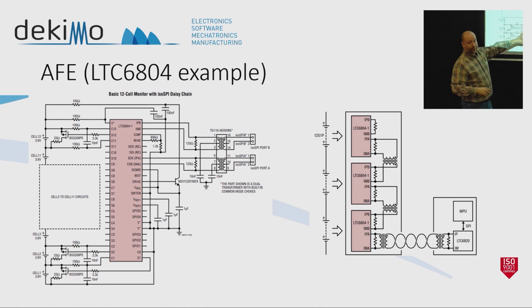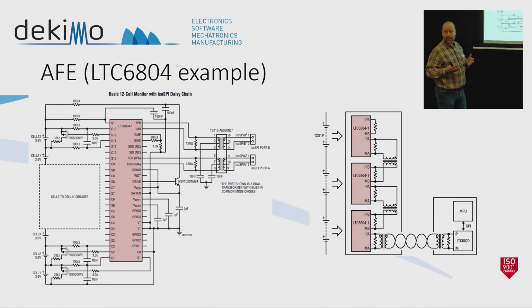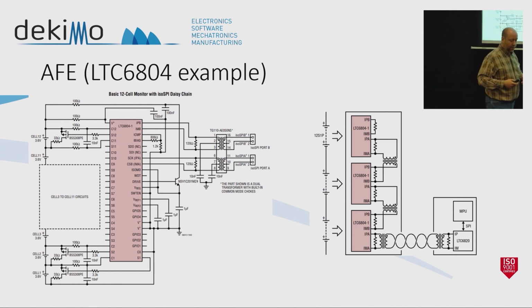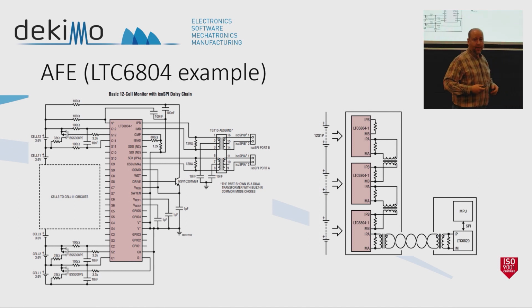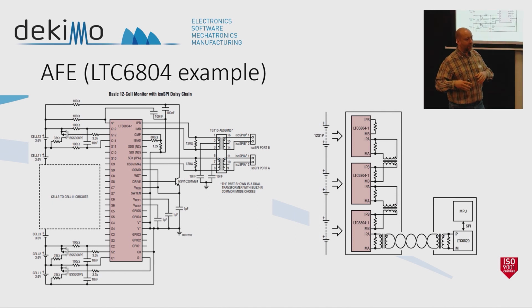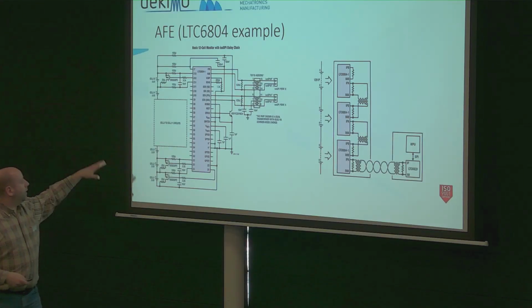The AFE can discharge every single cell separately in the battery pack. Then you have the chip, and a communication interface. What's often used in battery packs is an ISO SPI bus - basically an SPI bus that's galvanically isolated to prevent issues from different voltages, because with a battery of, say, 12 cells, if the voltage isn't high enough, you have to put more in series.